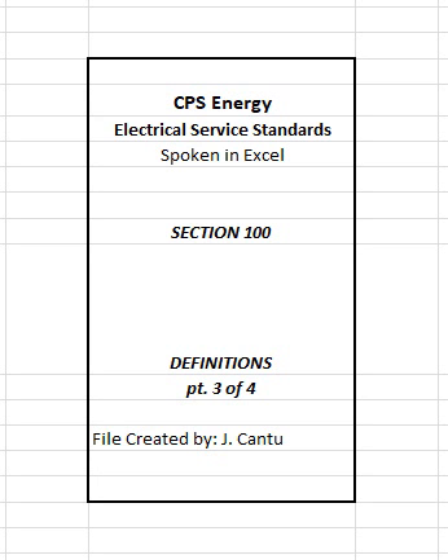Meter socket. Meter sockets are classified as either single-phase or three-phase and are either self-contained or transformer-rated. Self-contained meter sockets operate directly from the service voltage and load current. Transformer-rated meter sockets require current transformers, CTs, or voltage transformers, VTs, or both, to reduce the service current or voltage when they are beyond the ampacity of self-contained meter sockets.